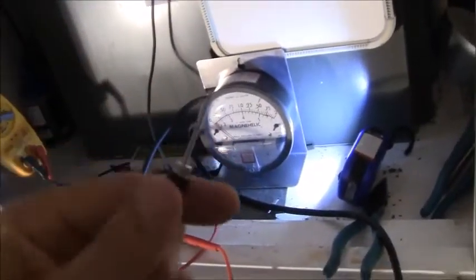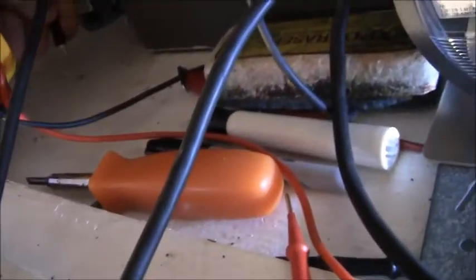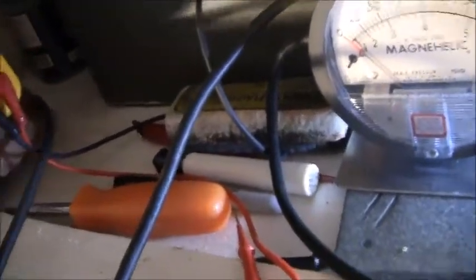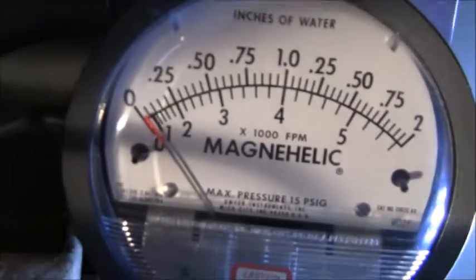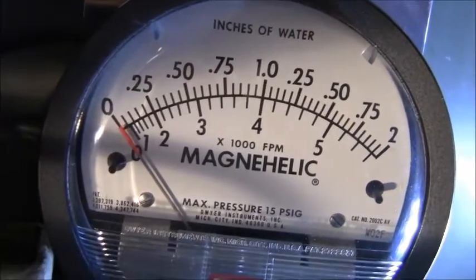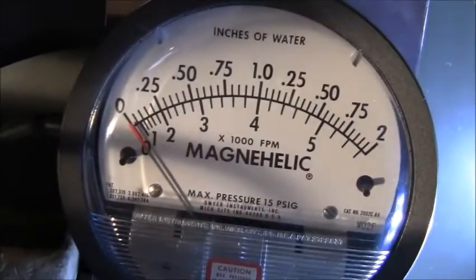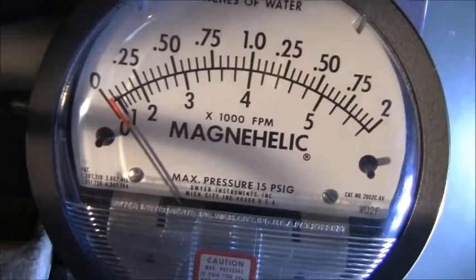So actually I have two needles. Let me switch. Okay, here is my low pressure port. Make sure your hoses are not kinked at all. Then I'm going to put this down into here, which is supposed to be getting the pressure down below the pre-filter. And then I'm going to see if this gauge reading moves. Now watch the gauge. I'm pulling it out, and then I'm going to put it back in, and you'll see the gauge move as I put it back in.